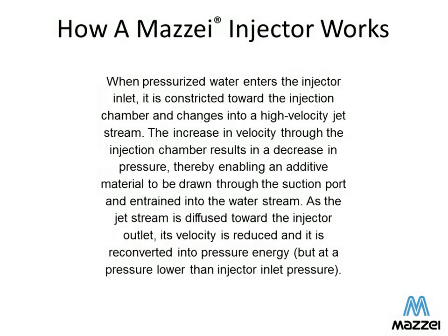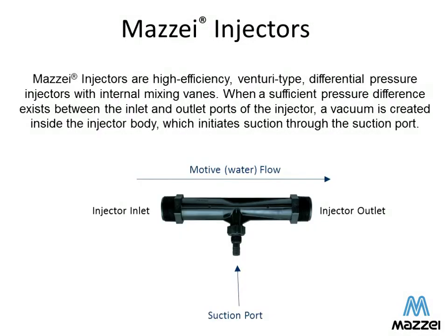So again, this is a lot of text. You could read through this. What I'd like to do is go back to this picture here to demonstrate how an injector actually works. So what you'll notice is as the water flow comes in through the injector inlet, you can see on the picture of the injector here, there is a constricting cone.